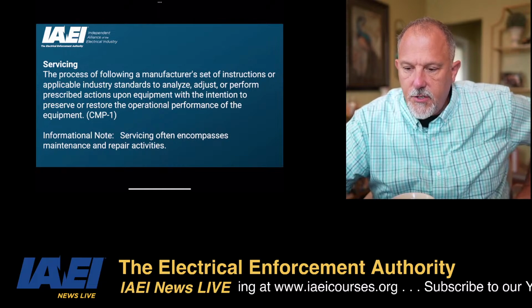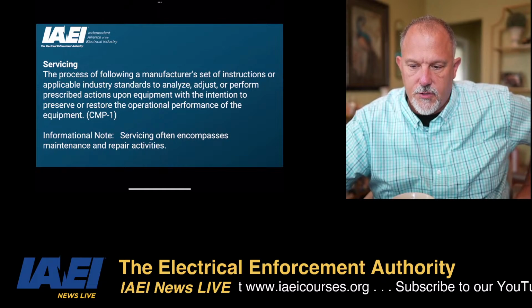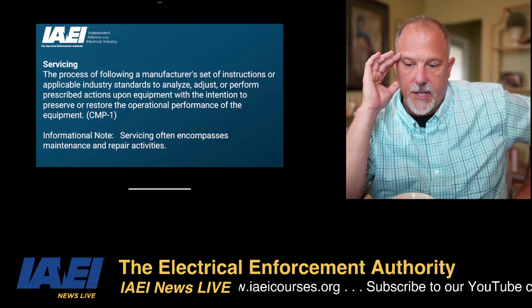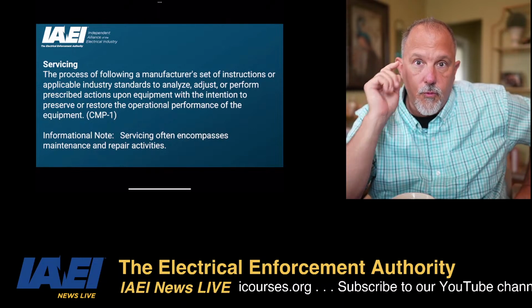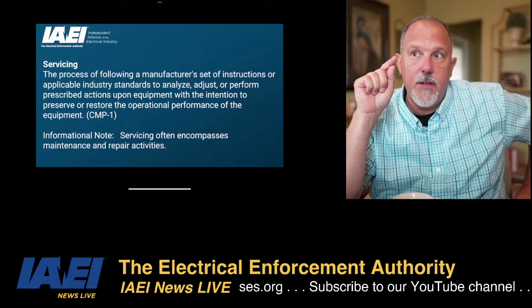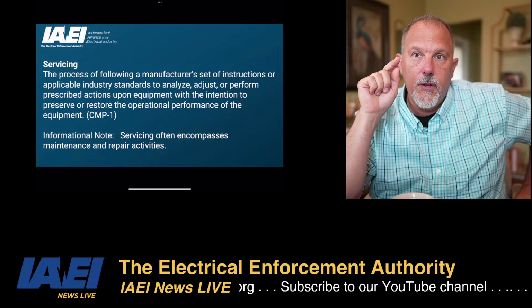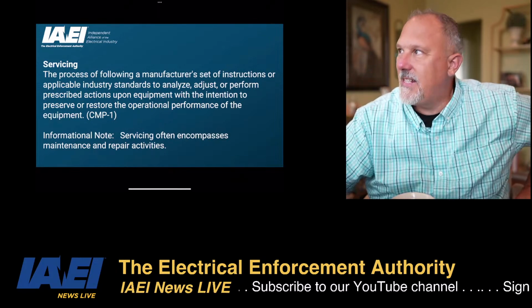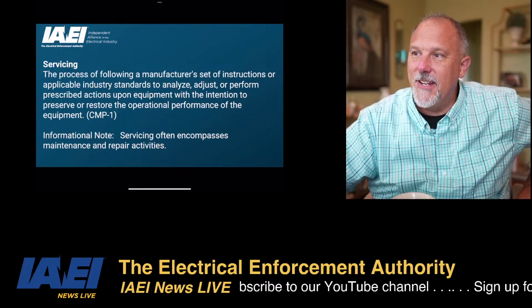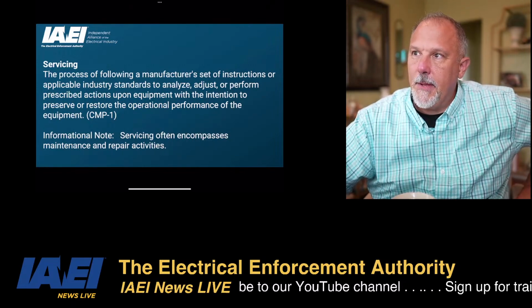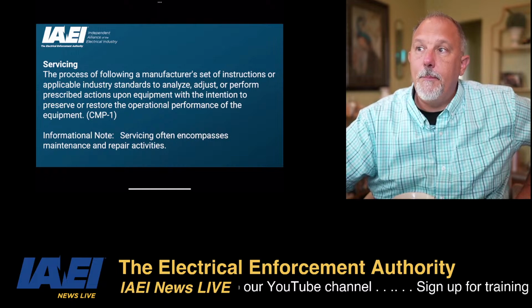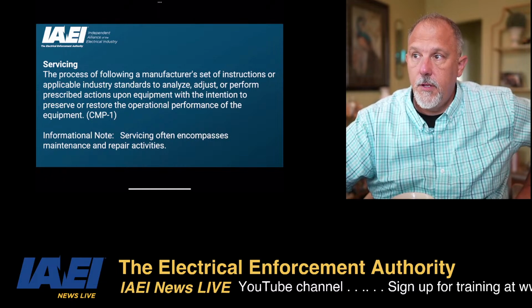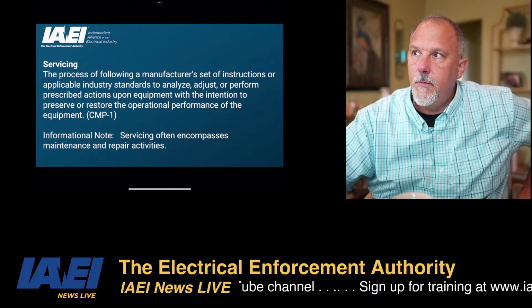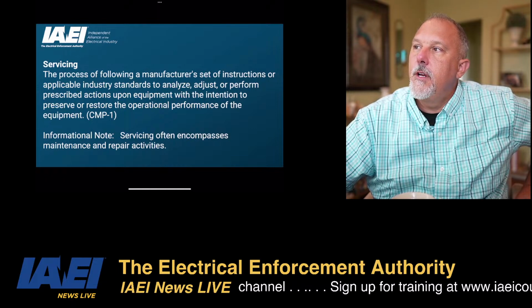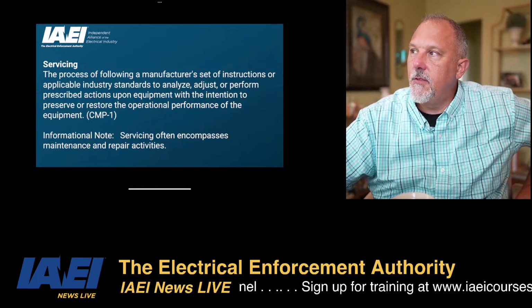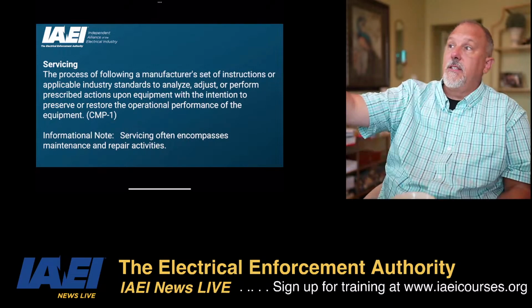So 700.2 says you can't recondition a transfer switch, but if I just call it servicing... right, but Daryl, I see your point on 700, because that's life safety equipment. But I'd argue 700.2 says reconditioned transfer switches shall not be permitted. I love that language—that's in the 2023 code.